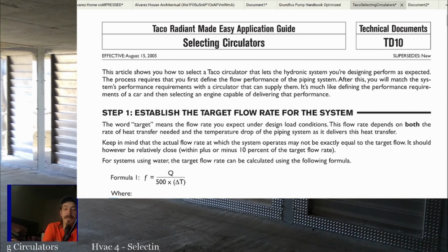You look at the specifications for your radiant floors or whatever, and you figure out what size boiler you need based on your load calculation, and you size your circulator. Use that system to size your circulator, and you'll be in good shape. All right. Any questions?